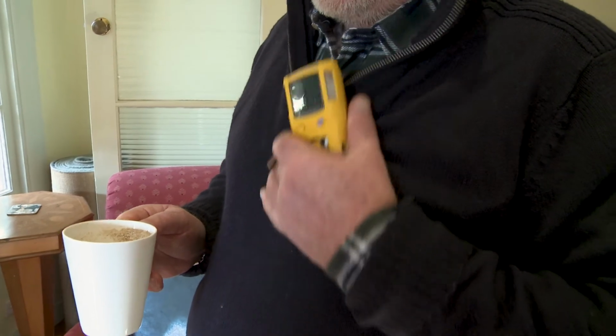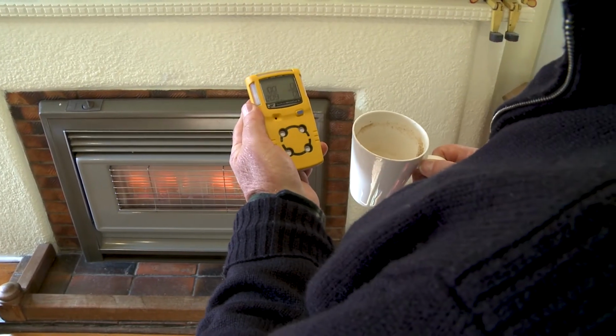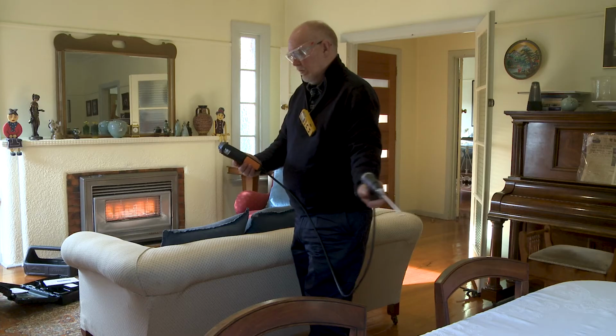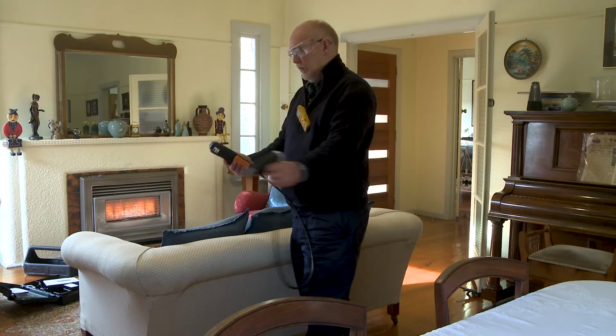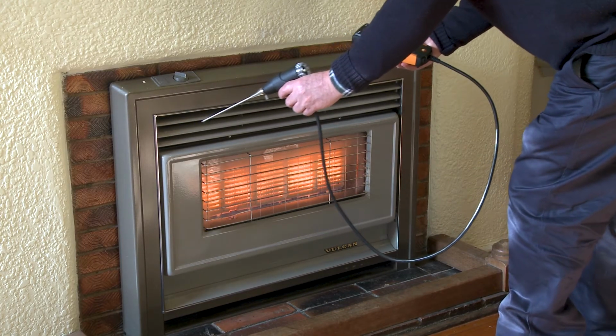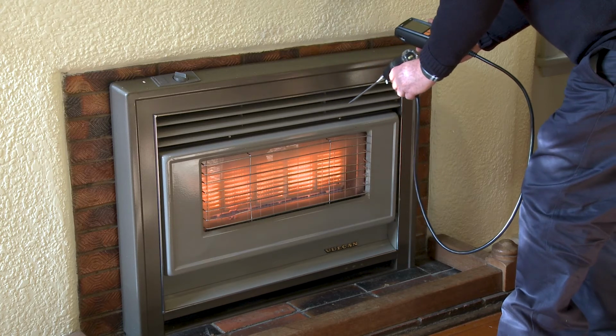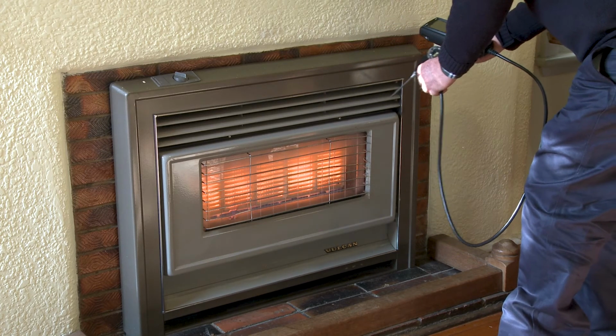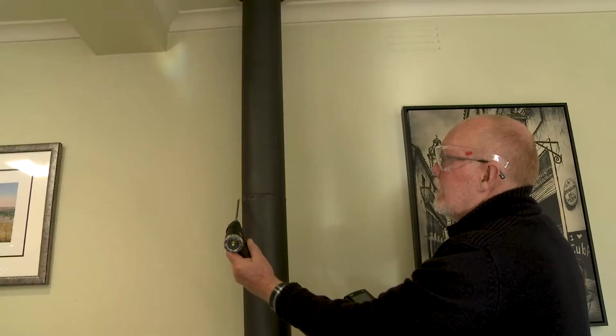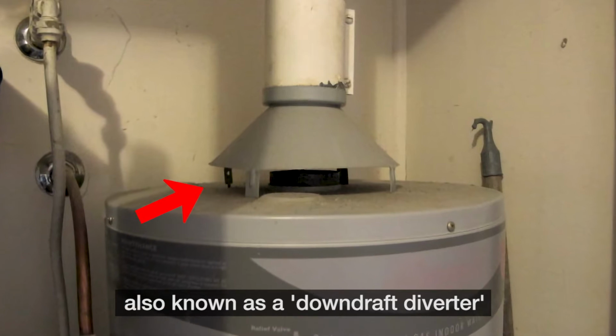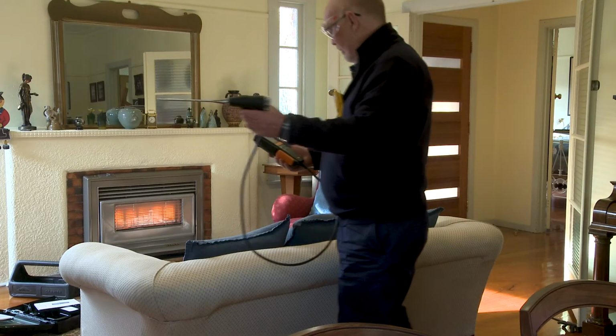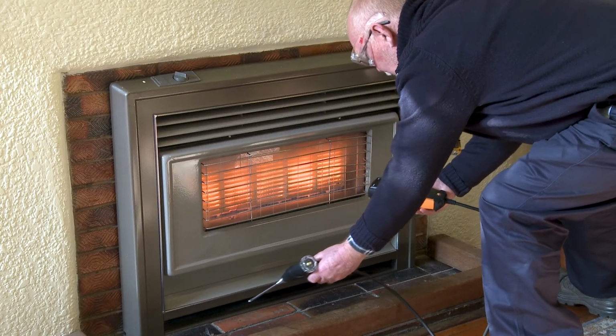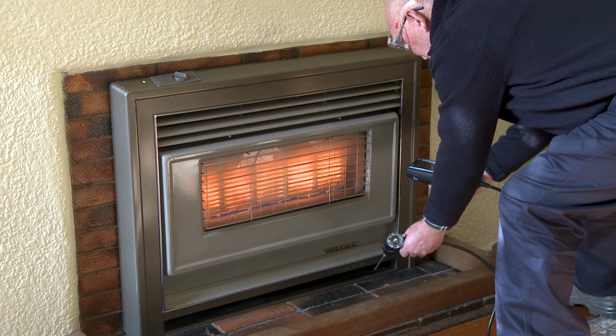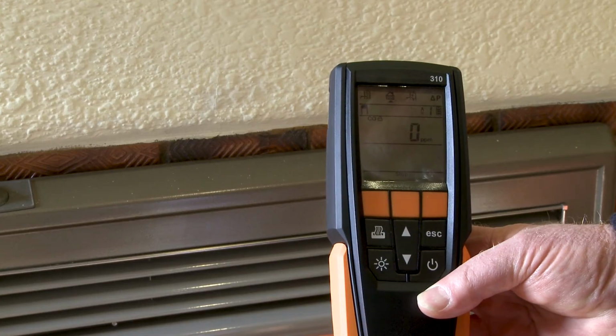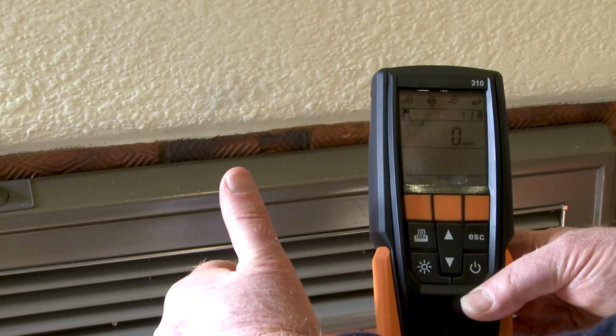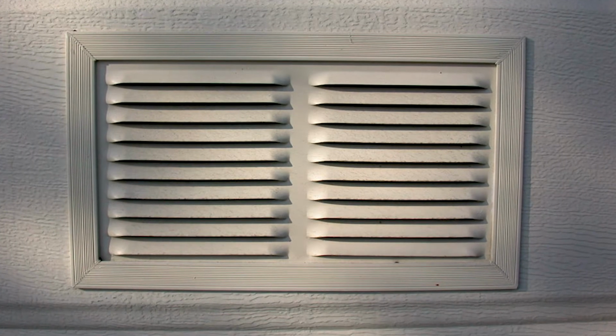Here's a hint. By having your monitoring equipment turned on during the warm-up, you can keep an eye on your CO exposure levels and also see if there's any change in the background reading. Depending on the appliance, place the CO sampling probe where spillage is likely to occur, such as next to the downdraft diverter openings, heat exchanger joints, flue connections, and at the base of flue product collection hoods. After the test, record a second background reading. The CO reading at the appliance must not be higher than the second background reading. If there is no CO spillage, then testing is complete and the appliance will be safe to use after any necessary vents have been installed.